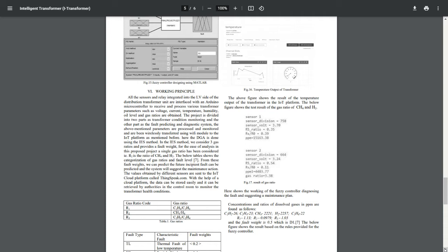The fault prediction system is developed using dissolved gas analysis, a method by which various gases formed in the transformer are studied for fault prediction. Using the gas sensors, gases such as hydrogen and methane levels are obtained and provided to the controller. The system studies different gas ratios specified and obtains the gas code. Fuzzy logic is a generalization of standard logic in which a concept holds a degree of truth between 0 and 1. Using fuzzy logic, gas ratio codes are studied and the corresponding fault weight is predicted.